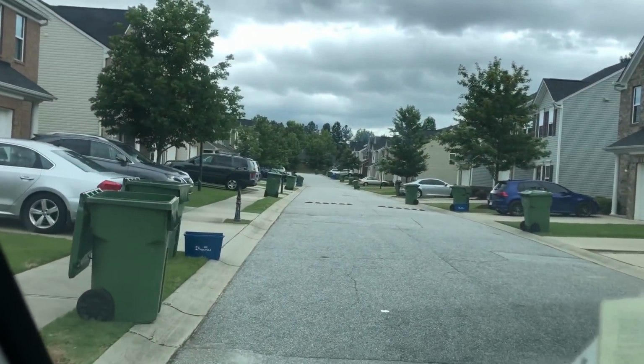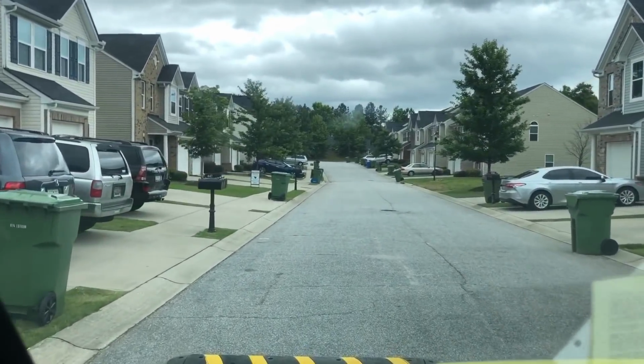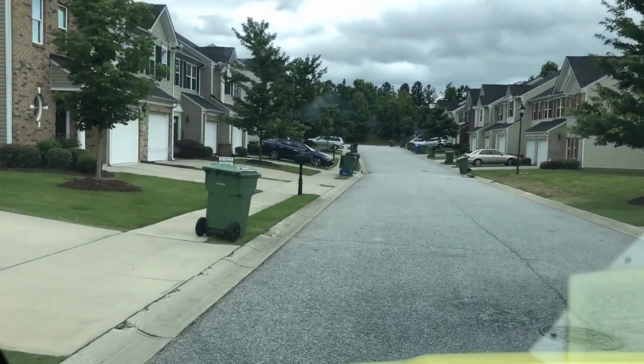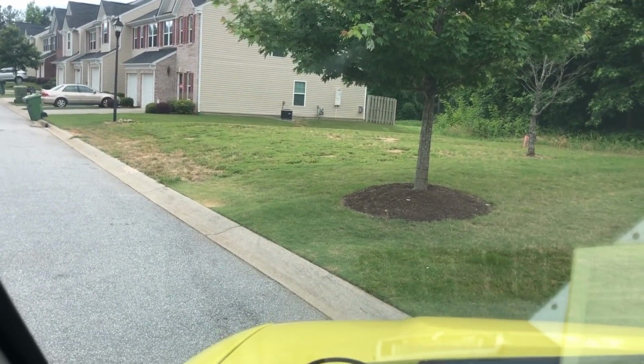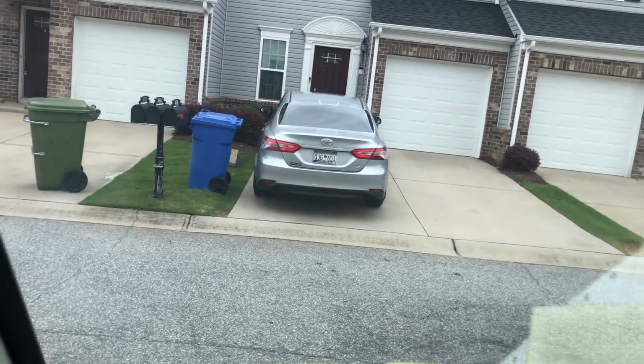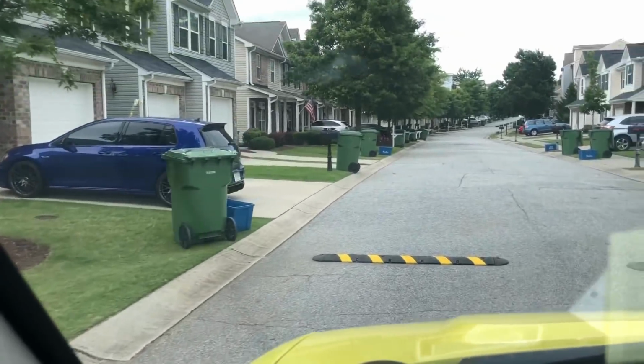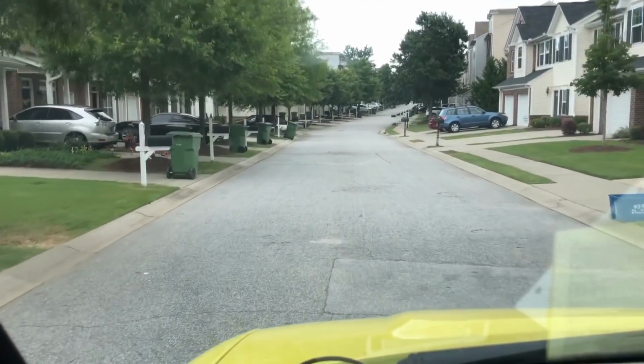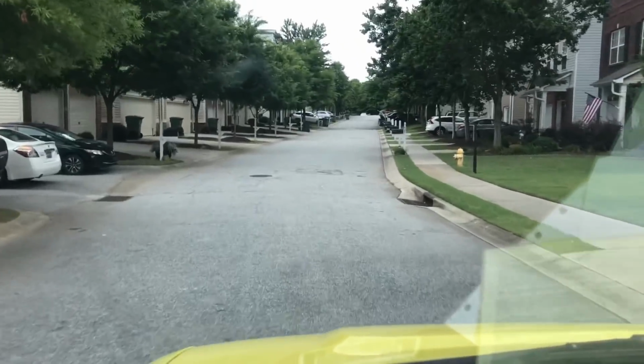I'm not really thrilled with not being able to see both ends of the drain pipes, but these multi-dwelling buildings, I'm going to assume they have a different code, which you can kind of understand, because the units that are in the middle of two other units, it would not be quite as easy to pipe it out. You would have to go out the front or the back, and that would cause extra turns, extra piping, whatever. So obviously for that reason they're allowed to pipe it the way we saw. Now I'm guessing at that. I've not seen that before. Not really crazy about it, don't like it.